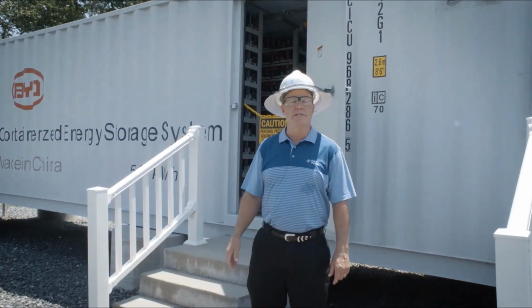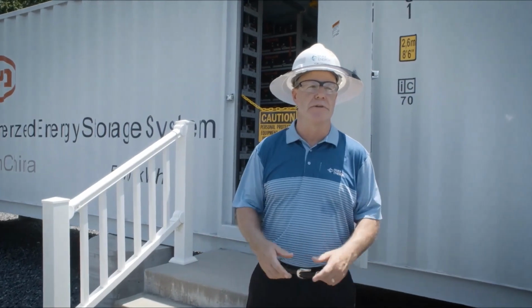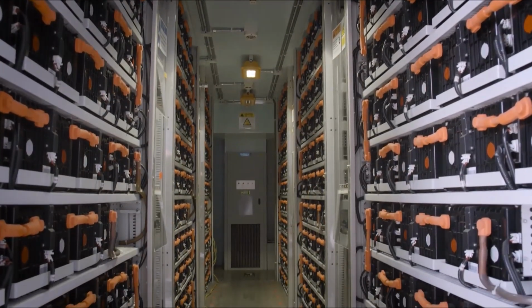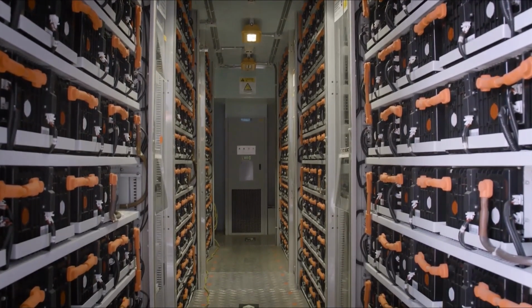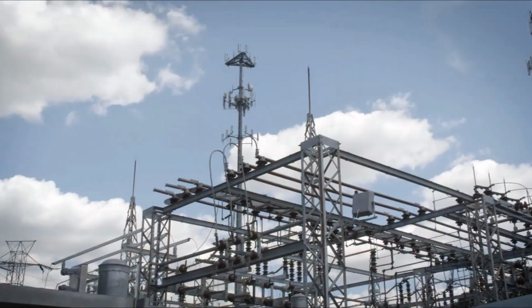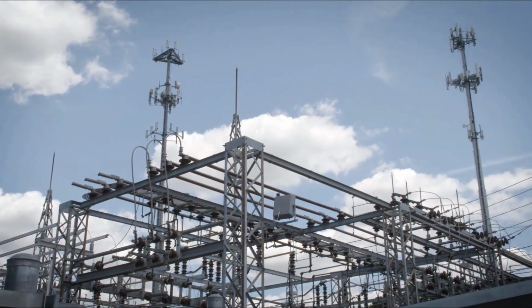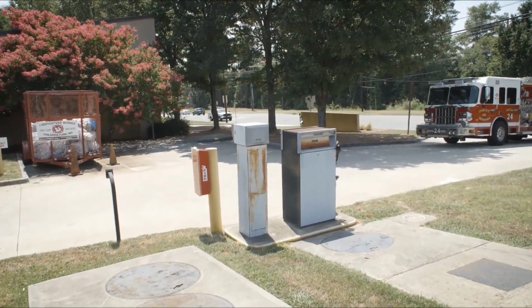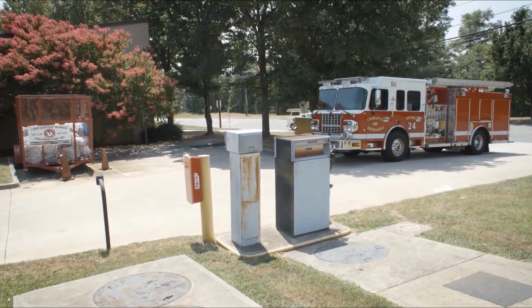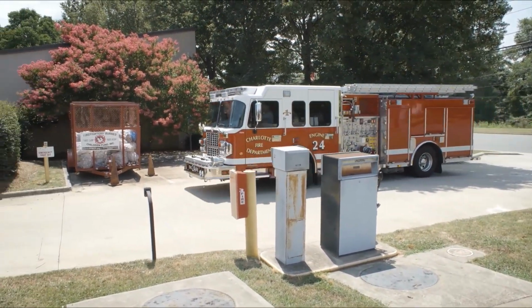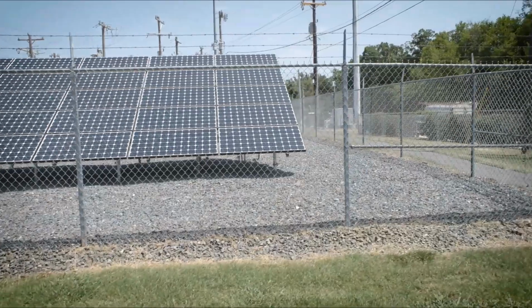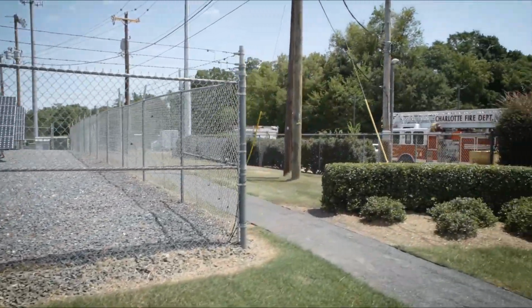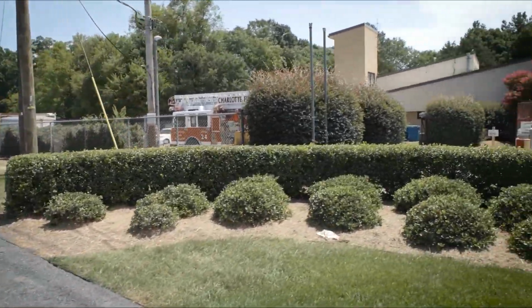This is a containerized energy storage system that contains 500 kilowatt hours of electricity, roughly a day and a half's worth of electricity to support the fire station in a typical operating mode. On June 17th of this year, we had an opportunity to disconnect from the grid and support the fire station for 26 hours, which gave us a really high level of confidence that should we have an emergency situation, we can expect to support the fire station for an extended period of time.